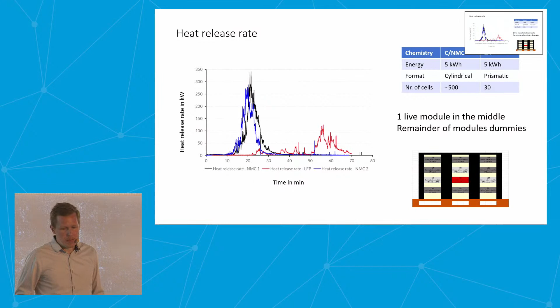No, this is still pre-test, without fire suppression. With the red module on fire, we could conclude that all the orange surfaces here exceeded 200 degrees Celsius in this free burning test. DNV has in their guidelines 85 degrees Celsius as criteria inside a dummy module when you test. And then it's a matter of heat transfer, of course, from surface to inside. We tried to have a worst case scenario or test setup with no passive barriers for heat transfer between the modules. So it was really to evaluate the fire suppression systems.